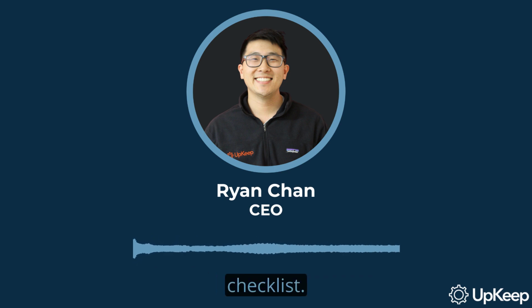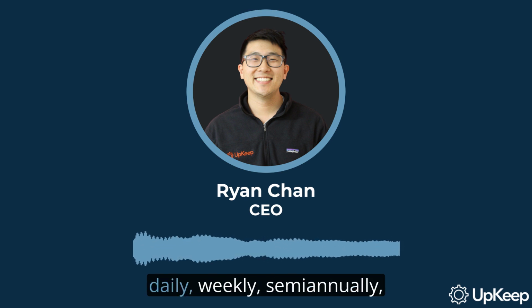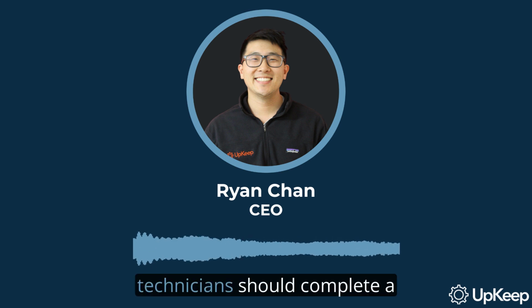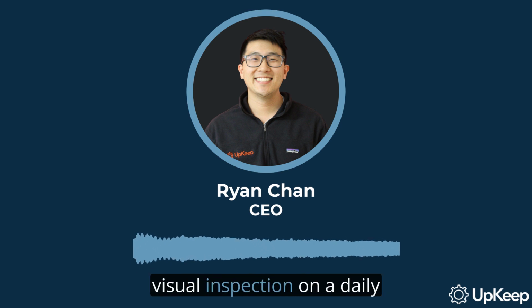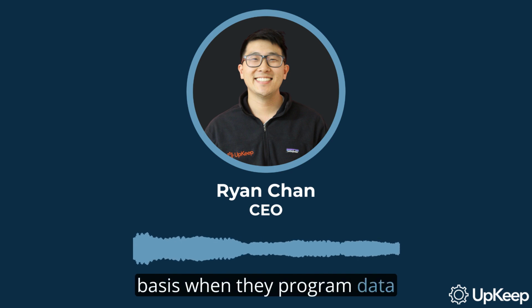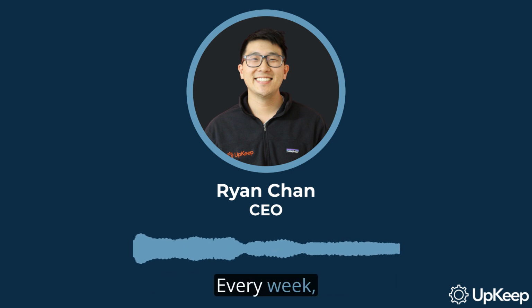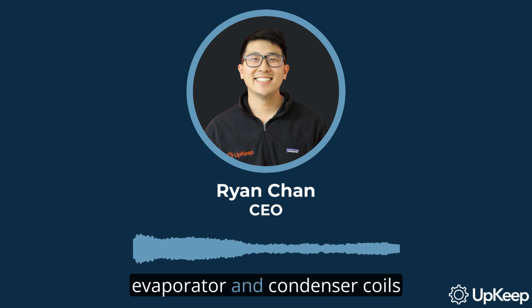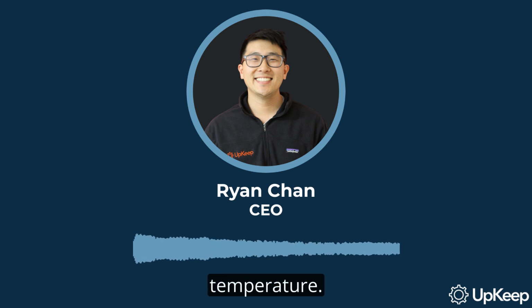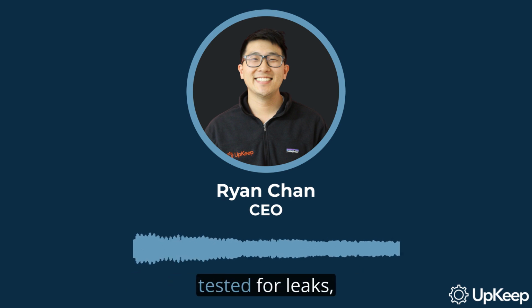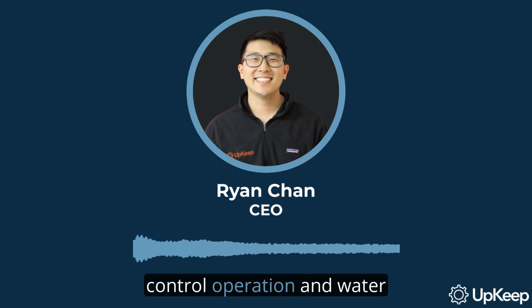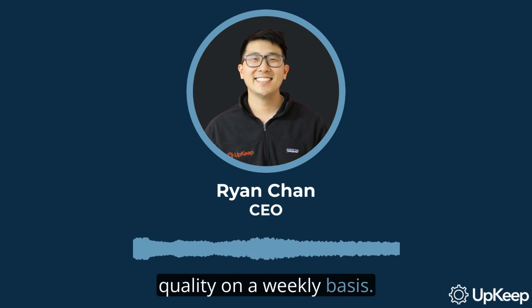Now let's take a look at the preventive maintenance checklist. The tasks for chillers can be daily, weekly, semi-annually, or annually, depending on the nature of the task. For instance, technicians should complete a visual inspection on a daily basis when they program data points and sequencing. Every week, someone needs to inspect the evaporator and condenser coils, as well as the motor temperature. Chillers should also be tested for leaks, control operation, and water quality on a weekly basis.